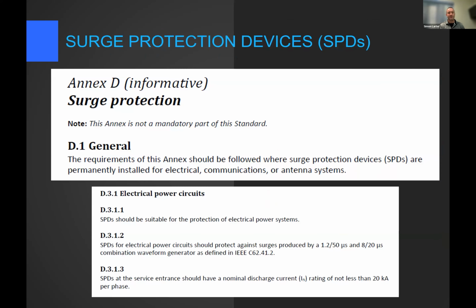Surge protective devices. You may or may not run across this. A lot of the time, those are going to be installed in the gear, in the transformer for sure, or the main distribution panel. That's often built in by the manufacturer. That would be type 1 versus type 2. And in any case, in CSA B72, whereas 780 has surge protection as part of the normative text, I couldn't convince the code panel in Canada of that. So it's in the informative section.